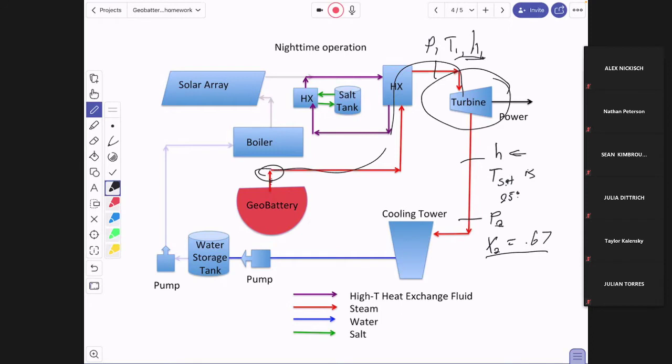This actually would be the case if I have what we call an isentropic efficiency of the turbine of 0.88 or 0.85, which is pretty reasonable. But that quality isn't reasonable. They really want to run those turbines so the moisture content doesn't exceed 12%, and it's beyond that now. The quality has to be above 88%, and the quality here is only 67. Now, they've got turbines that actually remove that moisture, and they're ones that are special for taking saturated conditions. This is a system that would put in superheat, and we'll talk about that a little bit later.